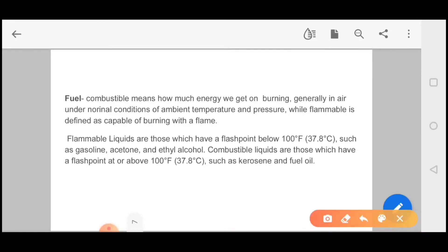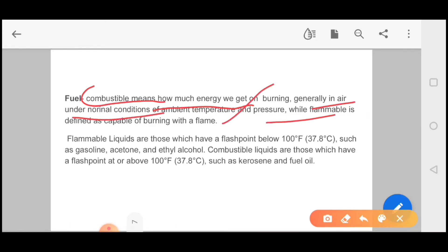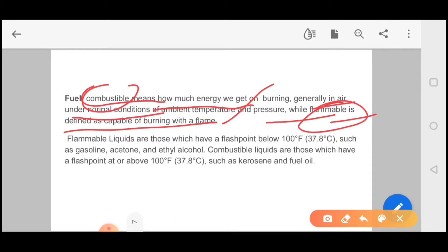Next we have fuel. There are two important words: combustible and flammable. Any solid or liquid when burned first produces vapor. Flammable liquids are those which have a flash point below 100°F, such as gasoline, acetone, and ethyl alcohol. Combustible materials have a flash point above 100°F, like fuel oil and kerosene. Combustible refers to how much energy we get from burning, while flammable refers to the capability of burning with a flame.